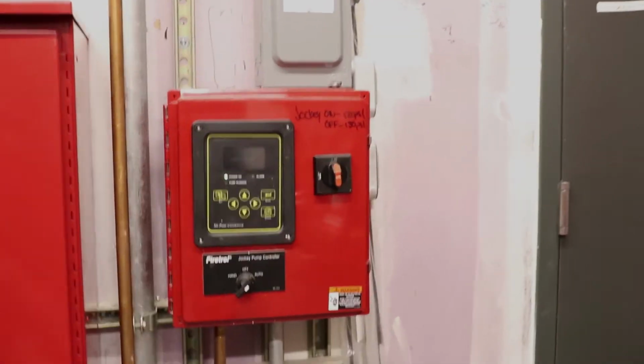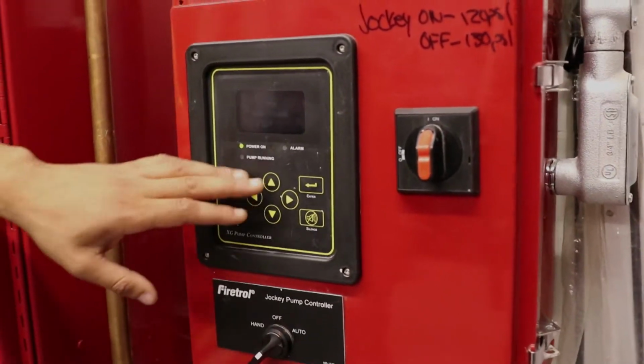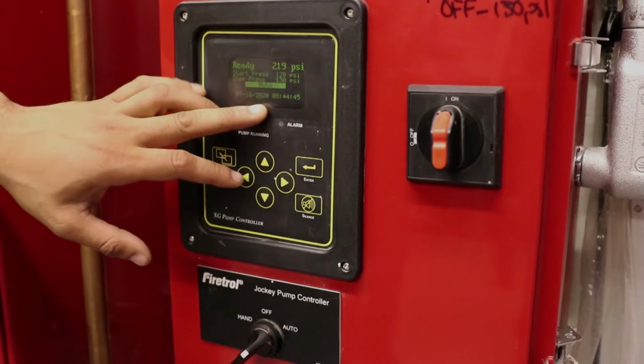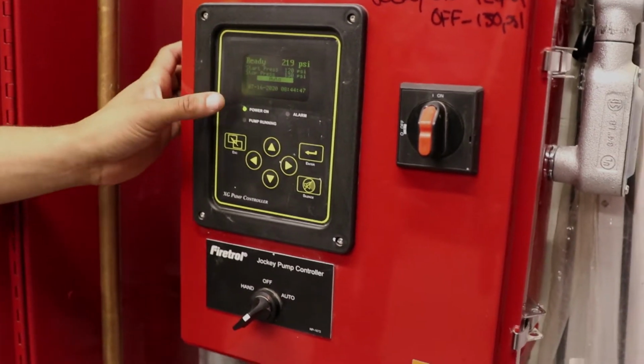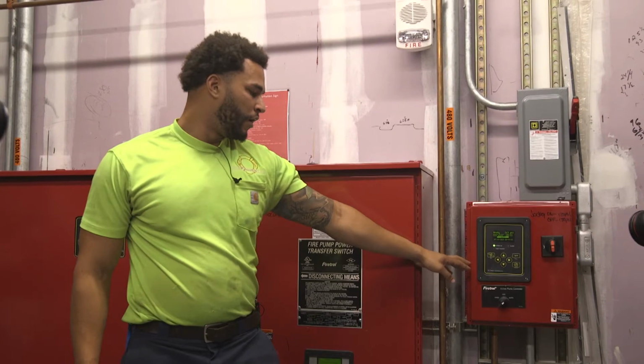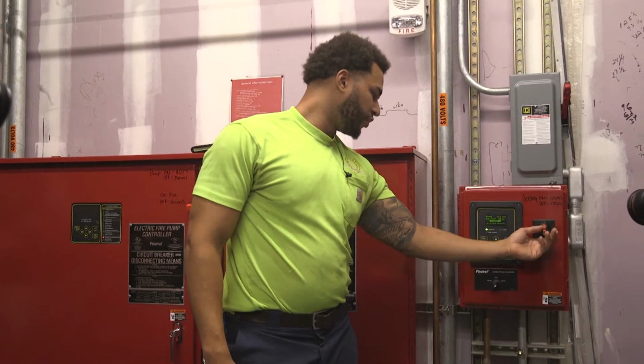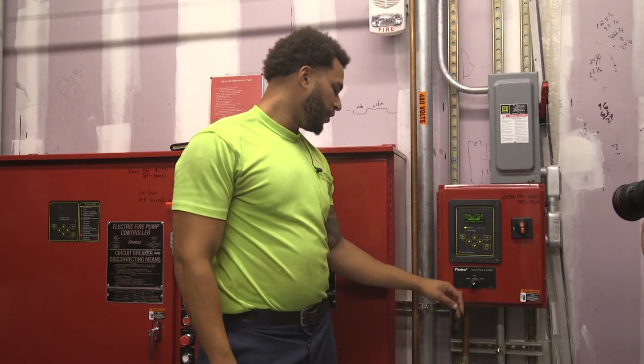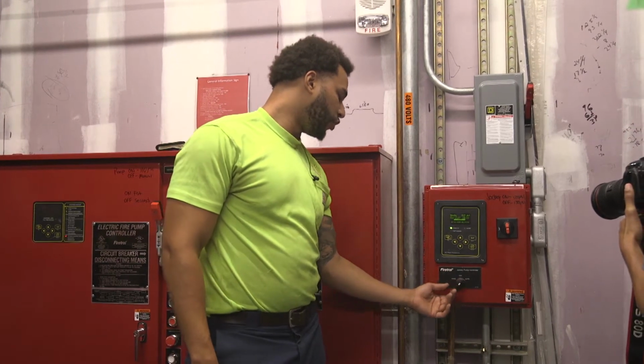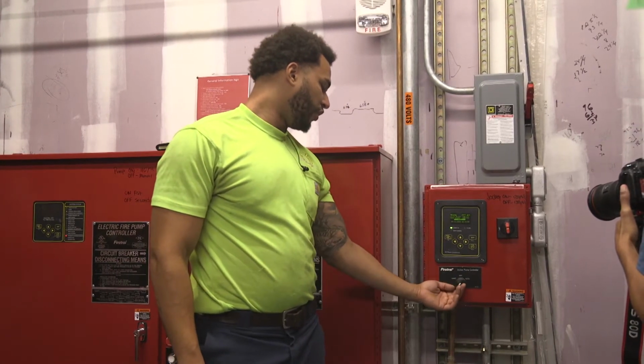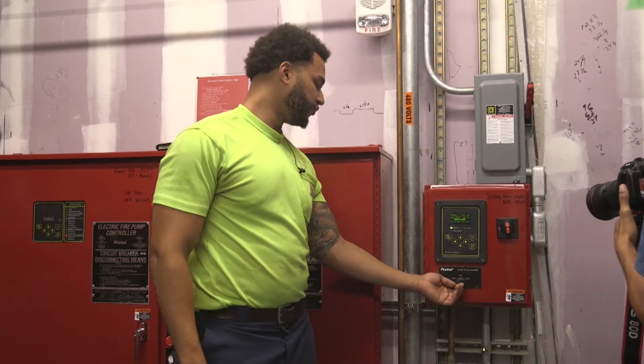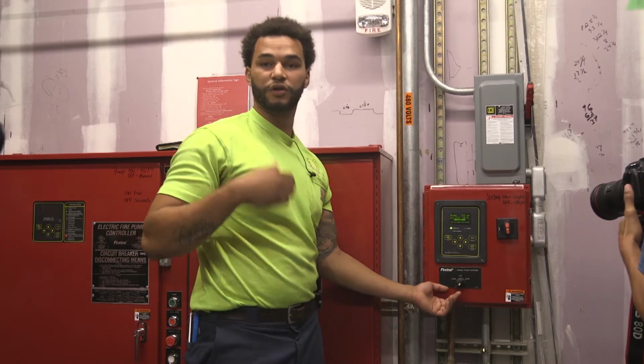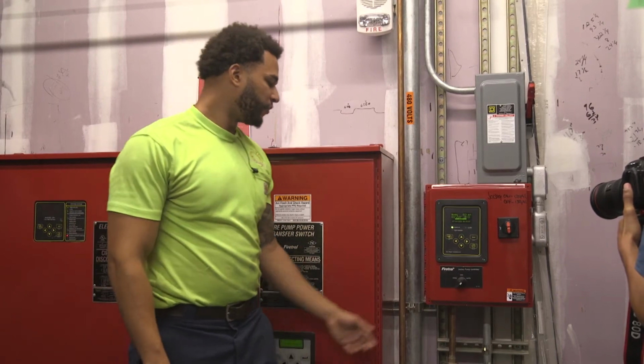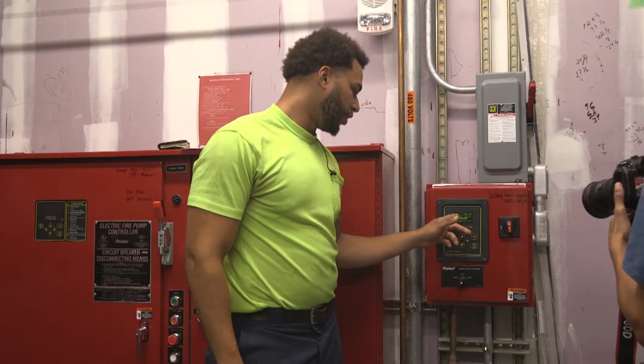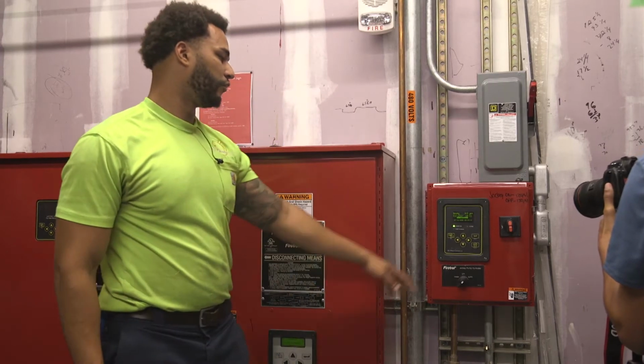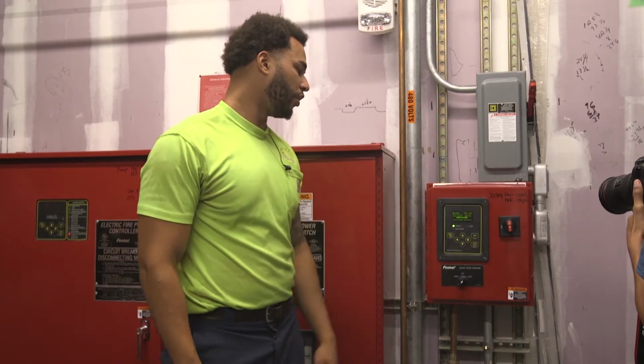Now we're here, we have our jockey pump controller. So on our jockey pump controller, you can read your system pressures, and you have your starts and stops, your cut-ins and cut-outs, as I'll say. Here are your switches. Well, you have your on and off switch for your controller. You have your auto. This jockey pump will always be in the auto position. You have the off position, and then you have the hand. If you switch this to the hand position, the jockey pump is just going to keep pressurizing on its own. When it's in the auto position, it will cut in automatically and it will cut out automatically at 120 on, 130 off.